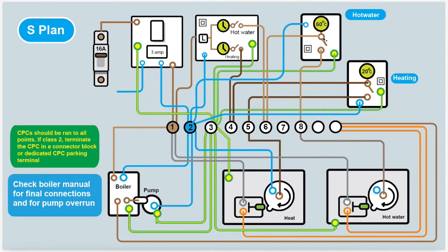You'll also notice I've run neutrals to every point as well. And again, sometimes the neutral's not needed, but it might be needed in the future. The thermostat, for example, the heating thermostat, sometimes they do require a neutral. There's a little heater in there to help the functionality of the thermostat and that requires a neutral.